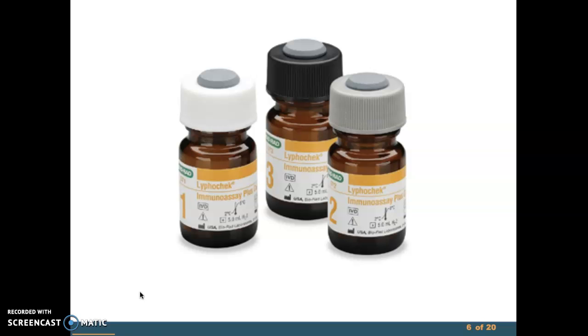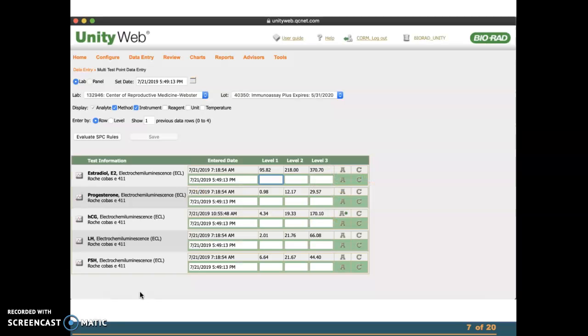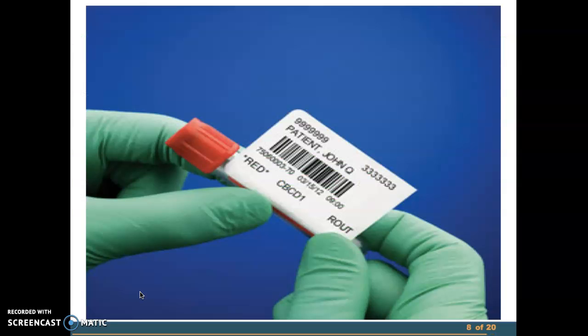If they're not in range, the line that corresponds to the reagent out of range will turn red, and the reagent needs calibrated whether it is due for a new one or not. It is important to note that with the database we use to evaluate quality control, as shown right here, it will make a result that is very close to being out of range show up as yellow. This is just a warning. However, if it is almost out of range again the next day, it will automatically change to red even if it technically still could pass. This situation will also warrant a new calibration.